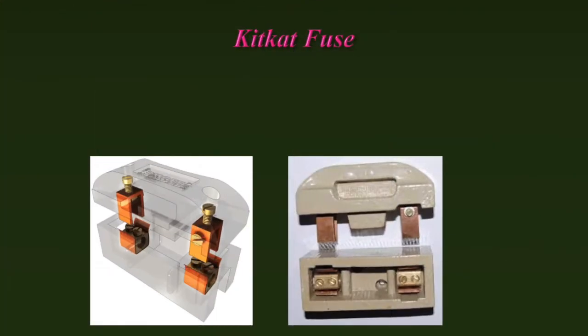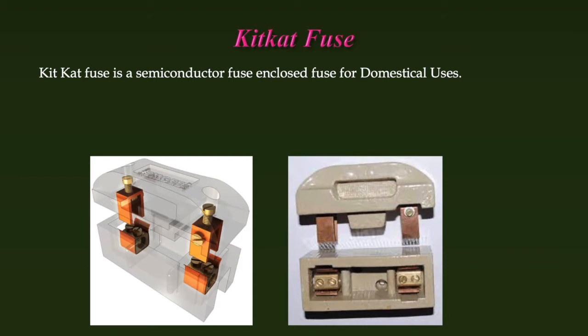First, it is the KitKat fuse. It is a very common fuse used almost everywhere, especially in domestic wiring. A metal conductor or fuse wire is used between two terminals. When the temperature increases due to heavy load above the rated load — say the maximum current in normal condition is 10 amperes — if the current becomes 15 amperes, the fuse wire heats and melts, detaching the connection.